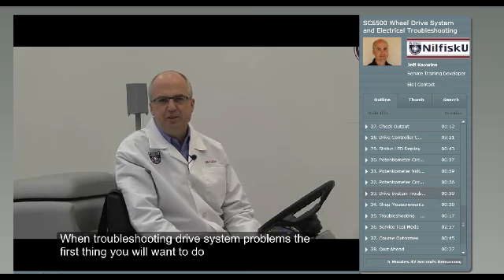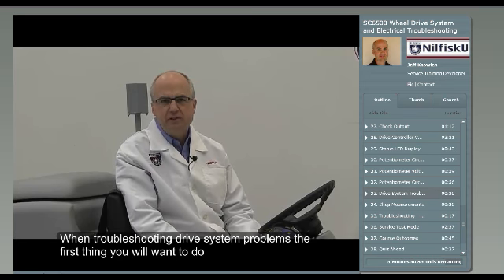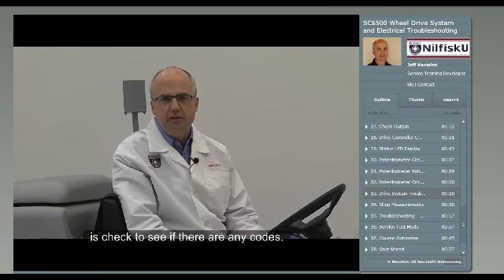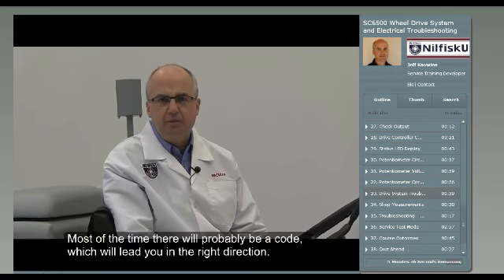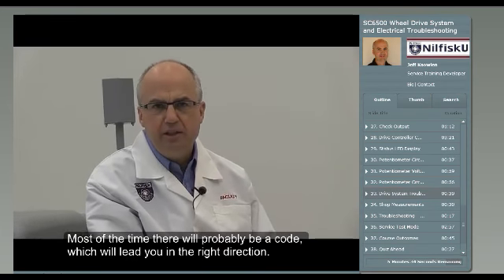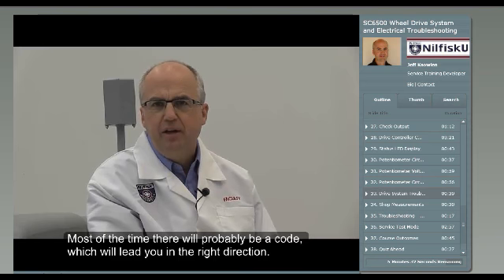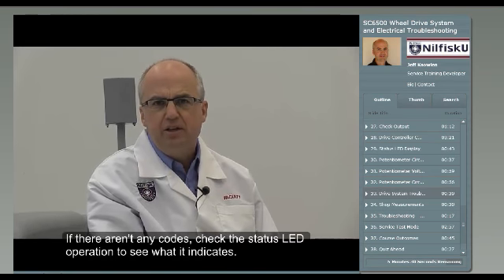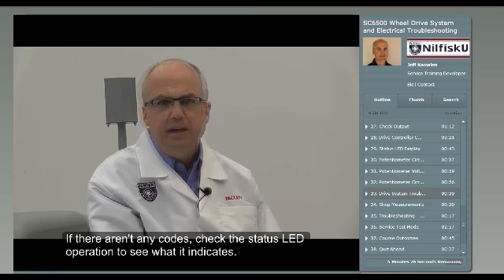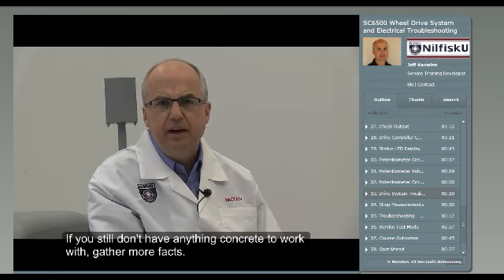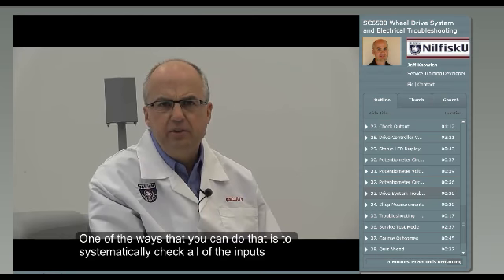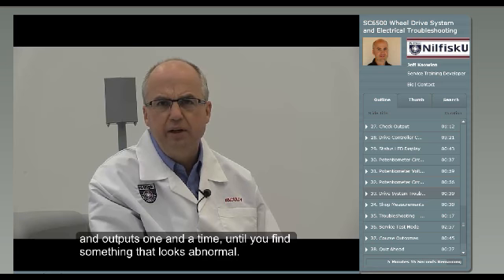When troubleshooting drive system problems, the first thing you will want to do is check to see if there are any codes. Most of the time, there will probably be a code which will lead you in the right direction. If there aren't any codes, check the status LED operation to see what it indicates. If you still don't have anything concrete to work with, gather more facts. One of the ways you can do that is to systematically check all of the inputs and outputs one at a time until you find something that looks abnormal.